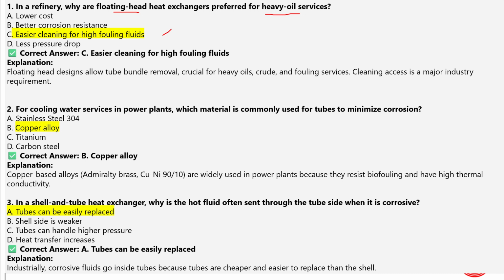So floating head designs allow tube bundle removal, crucial for heavy oils, crudes and fouling services. Cleaning access is a major industry requirement. The refineries are very congested, so the space available is very little. Because of that, we prefer these types of floating head heat exchangers.